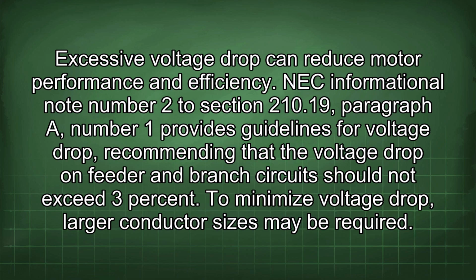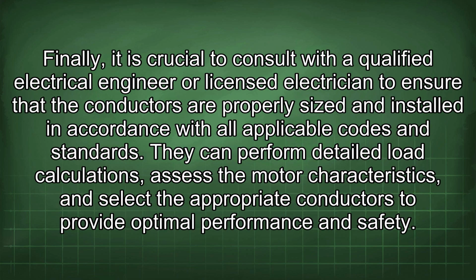NEC Informational Note Number 2 to Section 210.19(A)(1) provides guidelines for voltage drop, recommending that the voltage drop on feeder and branch circuits should not exceed 3%. To minimize voltage drop, larger conductor sizes may be required. Finally, it is crucial to consult with a qualified electrical engineer or licensed electrician to ensure that the conductors are properly sized and installed in accordance with all applicable codes and standards.